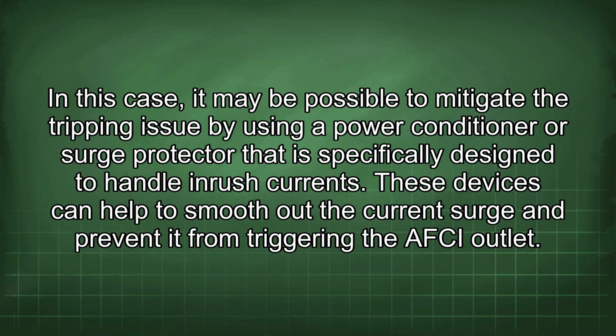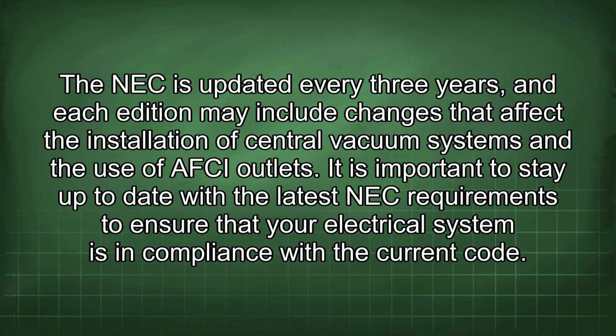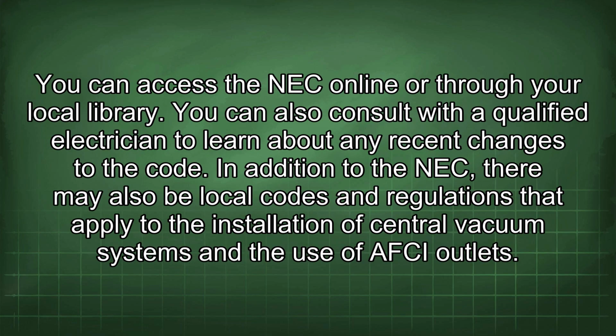In this case, it may be possible to mitigate the tripping issue by using a power conditioner or surge protector that is specifically designed to handle inrush currents. These devices can help to smooth out the current surge and prevent it from triggering the AFCI outlet. The NEC is updated every 3 years, and each edition may include changes that affect the installation of central vacuum systems and the use of AFCI outlets. It is important to stay up to date with the latest NEC requirements to ensure that your electrical system is in compliance with the current code. You can access the NEC online or through your local library. You can also consult with a qualified electrician to learn about any recent changes to the code.